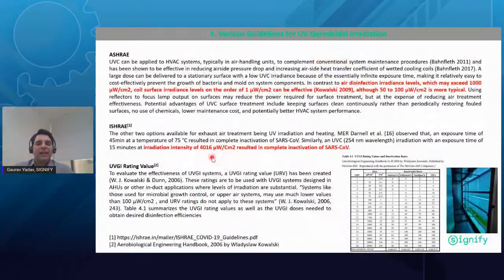These are the various guidelines for UVGI installation within the duct or within the AHUs. So ASHRAE is the American Society of Heating and Refrigeration engineers. They talk about the kind of irradiation level. If you are meeting those irradiation criteria, in a way you are meeting the ASHRAE guideline for indoor air quality improvement. Then ISHRAE is the Indian body of ASHRAE. They have also mentioned what the irradiation intensity within the AHU should be for the complete inactivation of SARS-CoV-2. So they are talking about much more stringent guidelines.